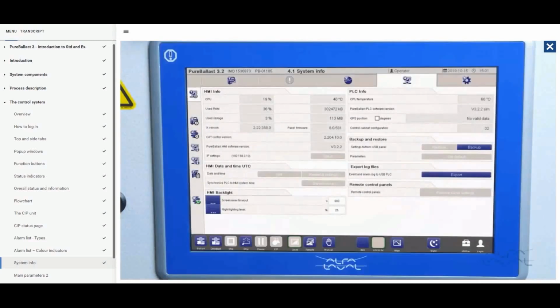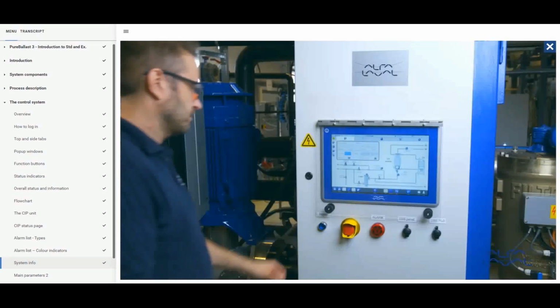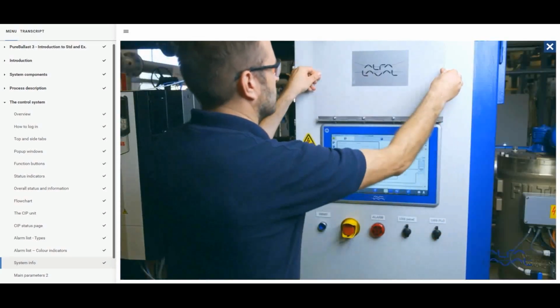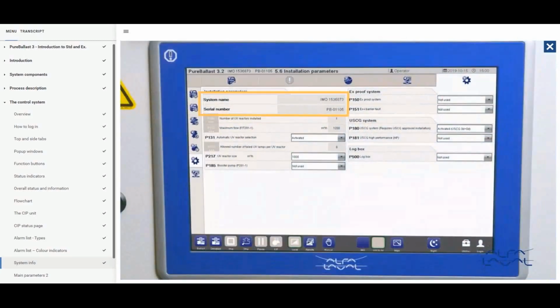Events and alarm history are logged in the control system and stored for at least 24 months. If the log box is installed, the log also includes components connected to the log box. The log files will not be deleted from the PLC during export. A list of all events that are logged can be found in the system manual under List of Logged Information. The log files are stamped with the system name and serial number entered in page 5.6.